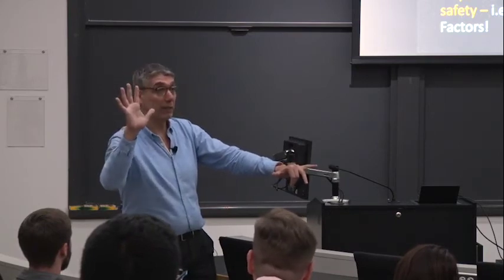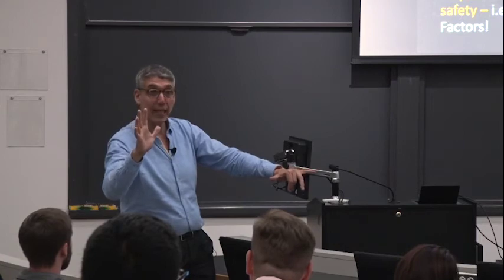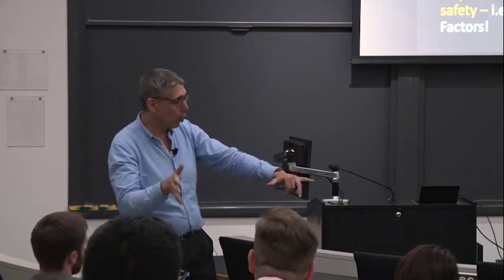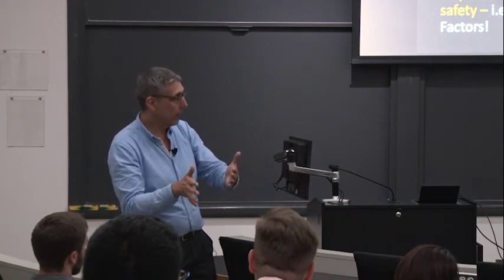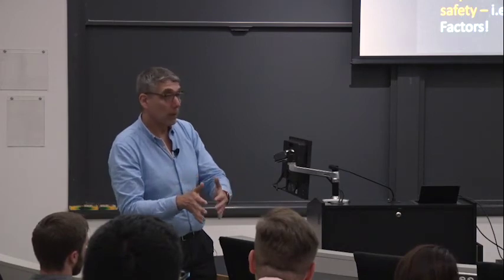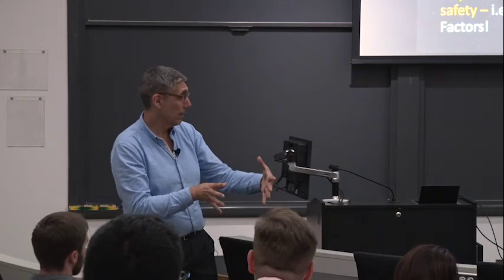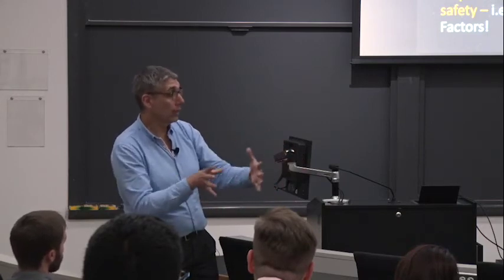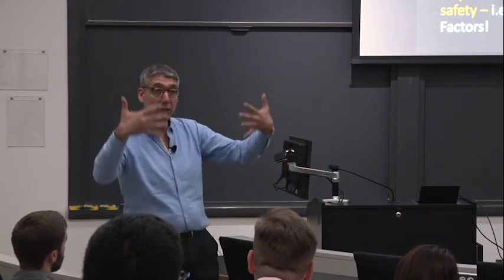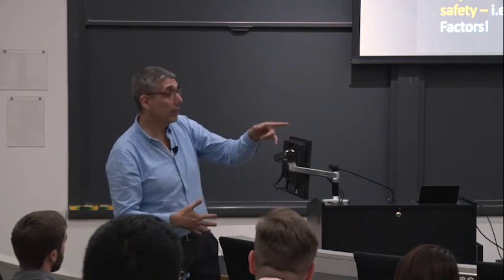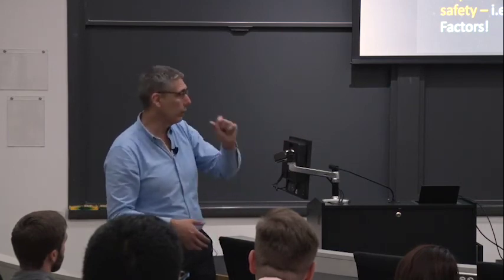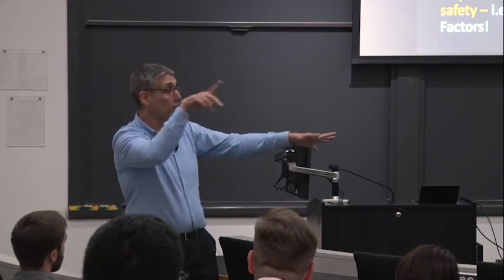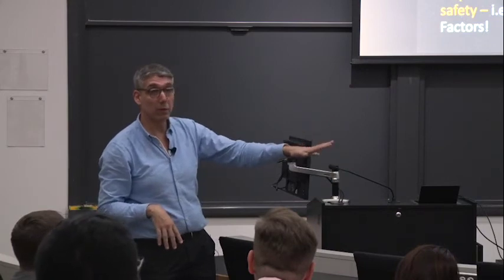So it is not the responsibility of the structural engineer anymore. They do not have to do a structural analysis because it will never fail. So the structural engineer remains in their comfort zone and they can design for cold and then insulate. Is that okay? Now, at that point, a series of testing labs, like Underwriters Laboratories and so forth, start developing, because now somebody had to test these things to make sure that they comply with the fire resistance requirements. And they start publishing their tables. And the table says, if you want 30 minutes, you need 10 millimeters. If you want 60 minutes, you need 20 millimeters. So it was a single table. Okay, so the fire engineers who were very concerned about life safety, and this was post-flashover, so it was not a life safety problem, were very comfortable saying, that is not our problem.